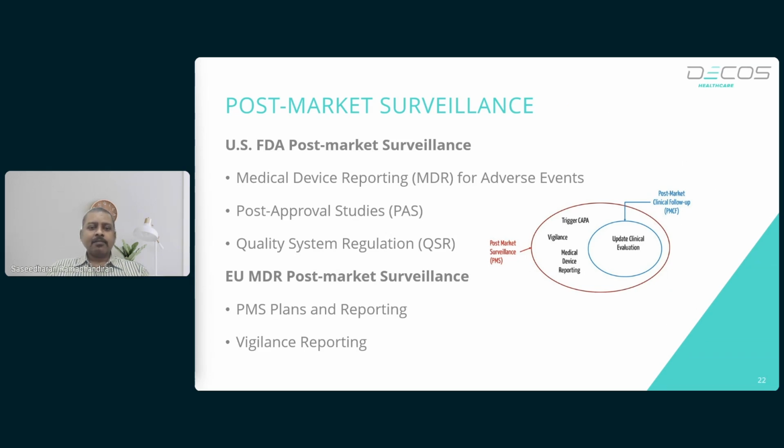This includes medical device reporting, MDR, for adverse events, where the medical device manufacturers are required to report adverse events and device malfunctions that could cause serious injury or death. This is mandated under FDA's Medical Device Reporting (MDR) system. Reports must be submitted within 30 days of becoming aware of an issue or within 5 days if the situation presents a significant threat to public health. The FDA's MedWatch system is used to streamline the reporting process, allowing manufacturers to submit detailed reports online.